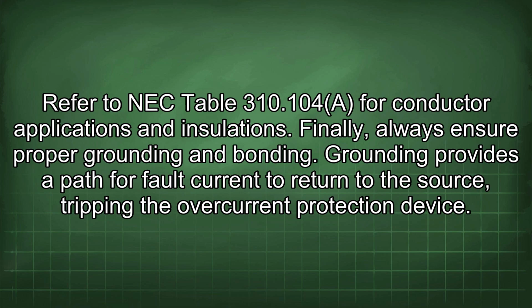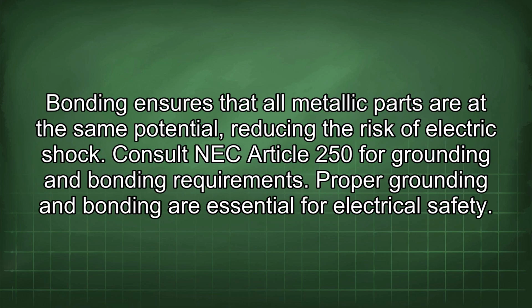Finally, always ensure proper grounding and bonding. Grounding provides a path for fault current to return to the source, tripping the overcurrent protection device. Bonding ensures that all metallic parts are at the same potential, reducing the risk of electric shock. Consult NEC Article 250 for grounding and bonding requirements. Proper grounding and bonding are essential for electrical safety.